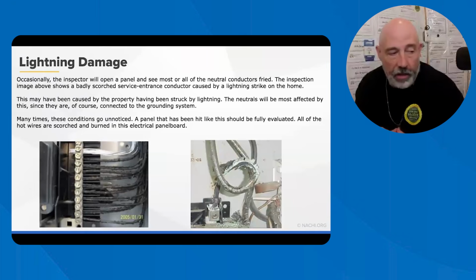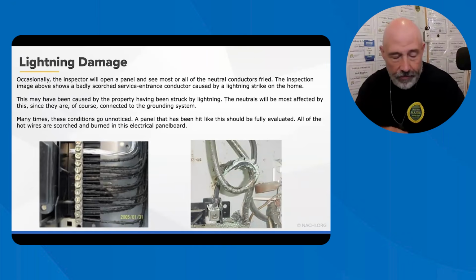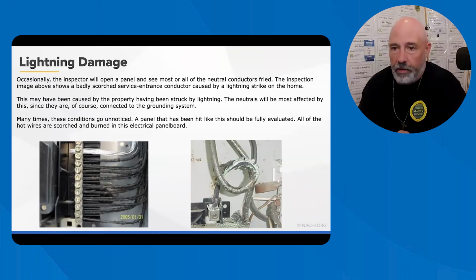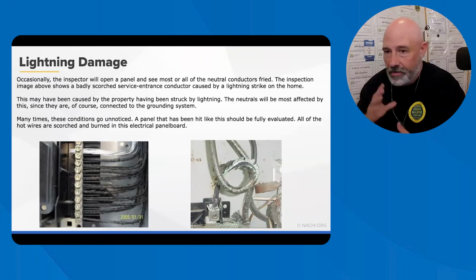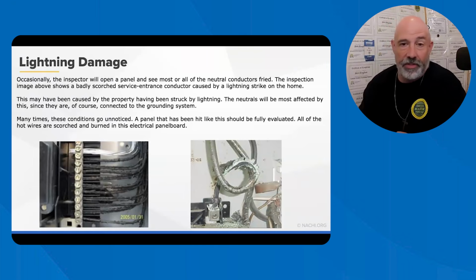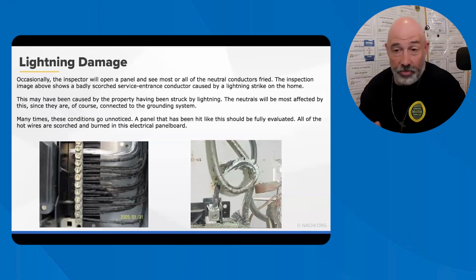Again, lightning damage. I've seen this with a solar panel install when they had an arc flash. All the neutrals were burned. It looked like a lightning strike hit it. It was so sad. And with a lightning strike, you never know what's going to happen. Lightning damage often affects the ground and the neutral conductors more than anything, because lightning can happen from the ground up or it can happen from the sky down. Doesn't matter.